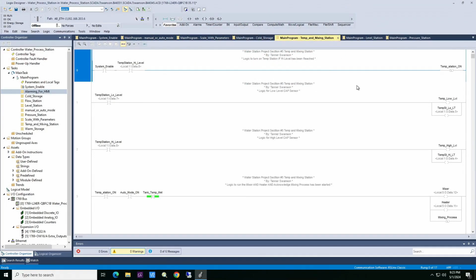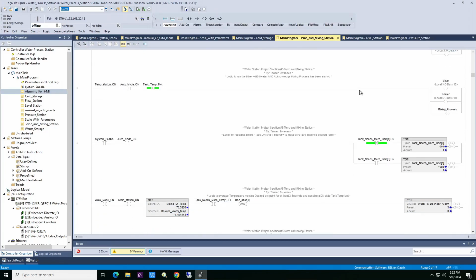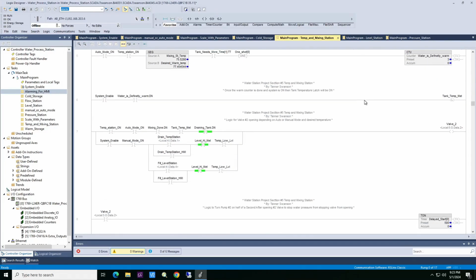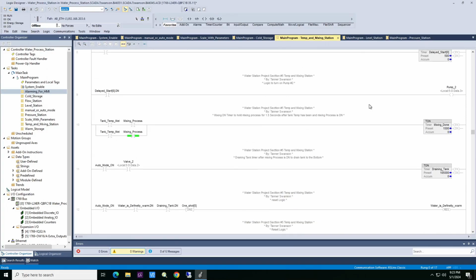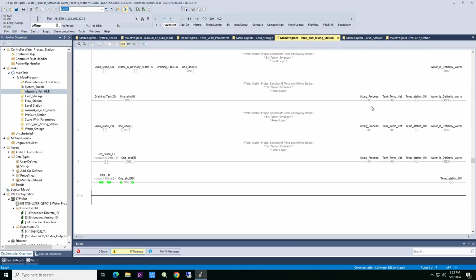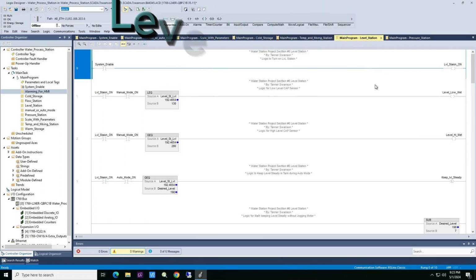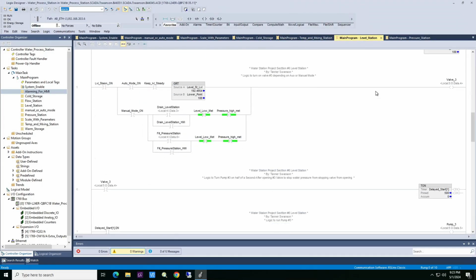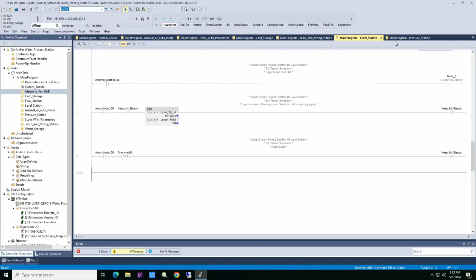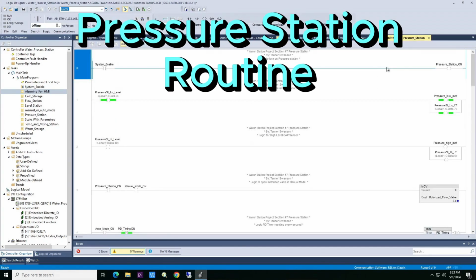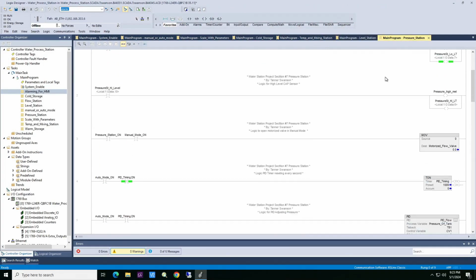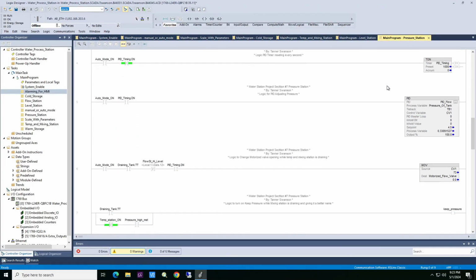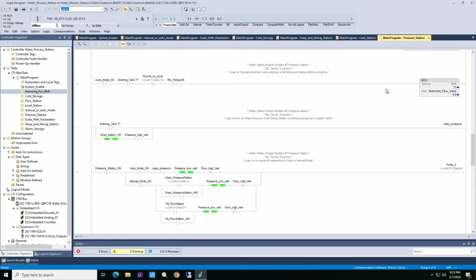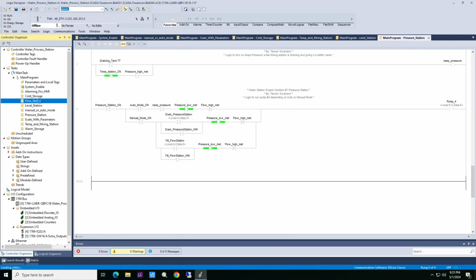Here's my temperature station to make sure that the temperature is at its warm temp before going on to the next station, using averaging. Here is the level station routine. The pressure station routine with the PID controller to control pressure, depending on opening the motorized valve to a certain opening. And then in manual mode, it opens the valve 100%.